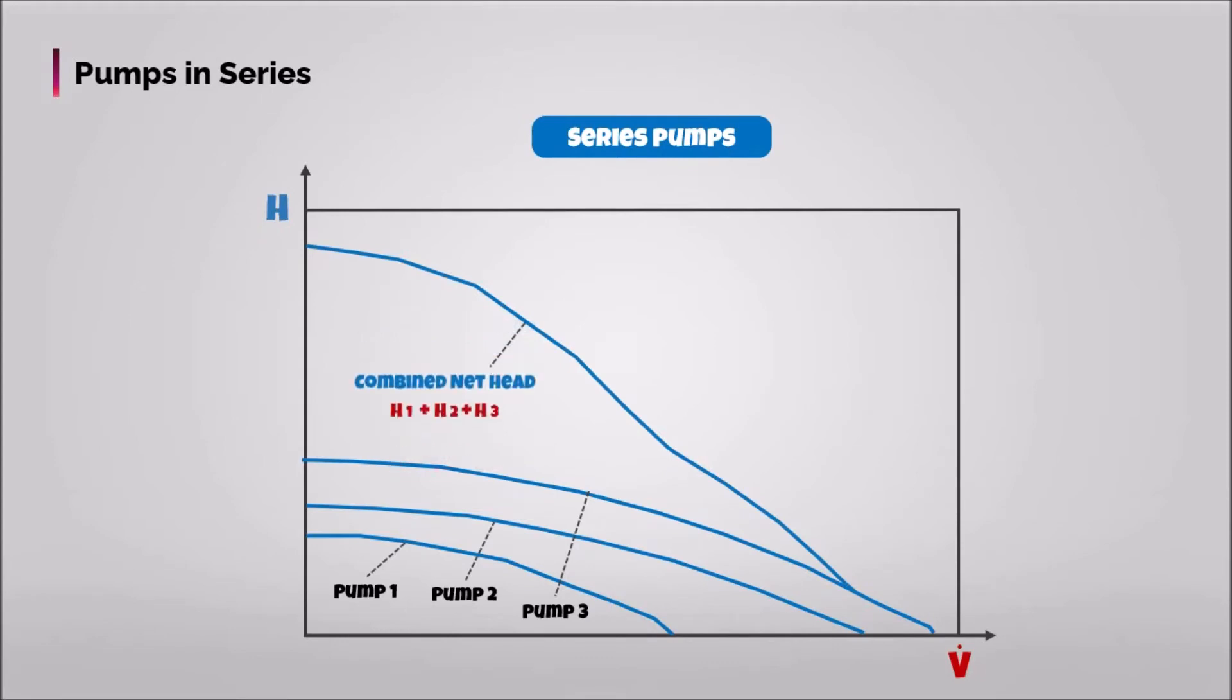However, to avoid pump damage and loss of combined net head, any individual pump should be shut off and bypassed at flow rates larger than the pump's free delivery, as indicated by the vertical dashed red lines.